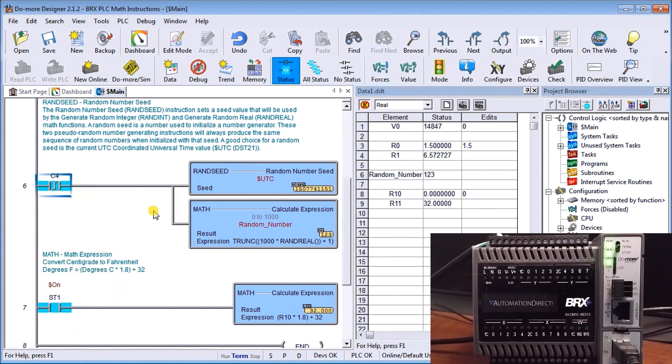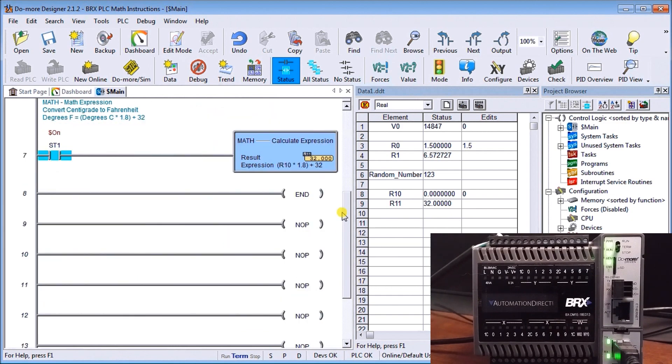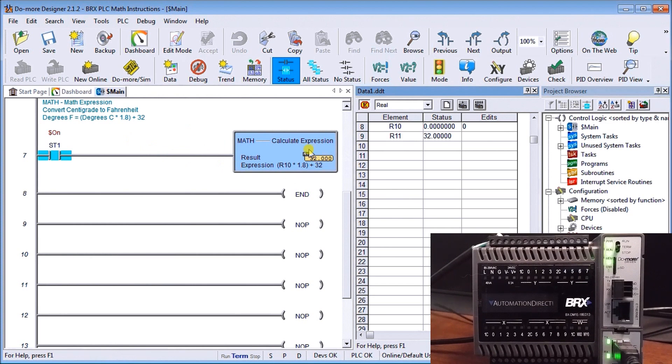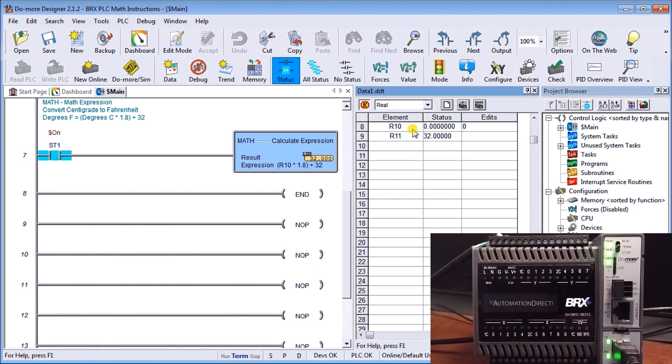The next instruction is probably one of the most powerful ones that we'll be using all the time, and that is the calculate expression. This is our math, an expression that will calculate exactly what we want to do with anything here. We have an output, in our case R11, and we're calculating Celsius to Fahrenheit degrees so we can display our information. If we put in a Celsius, we'll get a corresponding Fahrenheit. Right now we have R10 equal to zero, and zero represents 32 degrees Fahrenheit.